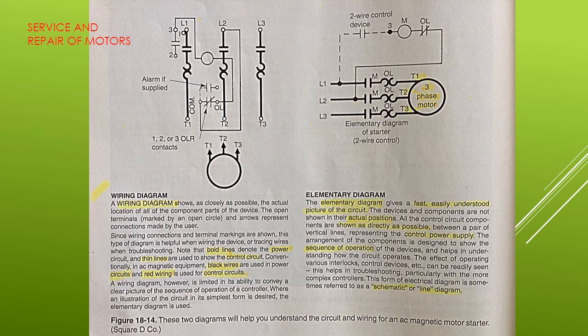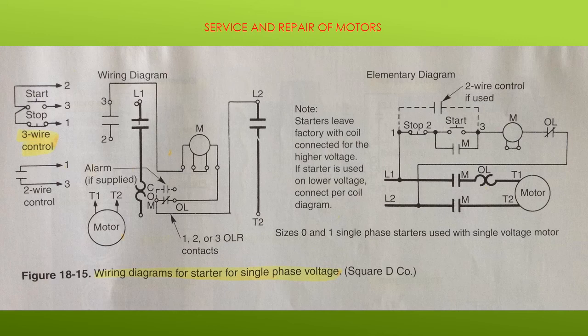Figure 18-14 describes a wiring diagram and an elementary diagram. Knowing how to read these diagrams will help you diagnose problems and make the connections correctly. The diagrams for single-phase motors are similar to those created for three-phase motors. Counting the number of terminals on the motor or the number of legs in the power supply will help you determine the phase of the diagram. There are many details in the wiring and elementary diagrams as shown in figure 18-16.